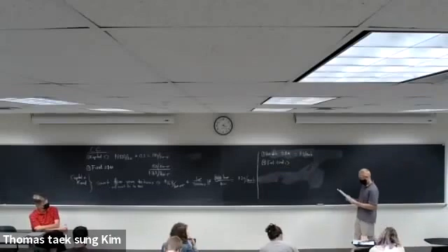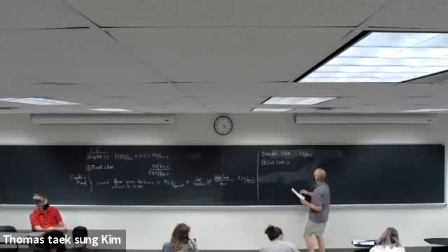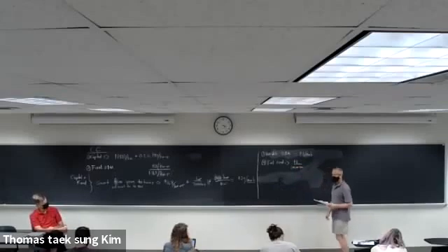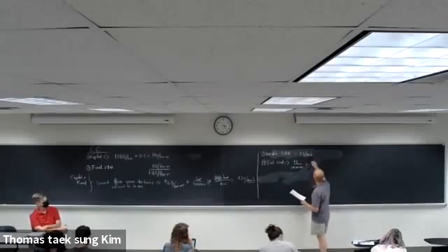Multiply the cost of fuel, which is in million BTUs, by the heat rate, which is in BTUs per kilowatt hour. So let's start with the $3 per million BTUs, times the heat rate, which is 7,000 BTUs per kilowatt hour.